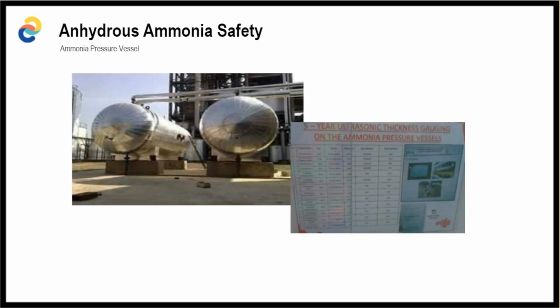Ammonia pressure vessel. An ammonia pressure vessel should comply with the ASME Pressure Vessel Code, Section 8, Division 1. This covers the design, fabrication, inspection, and testing during construction of the pressure vessel. Manufacturers producing pressure vessels shall provide data affixed on the nameplate.